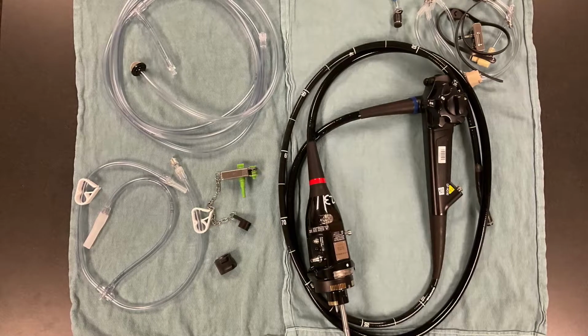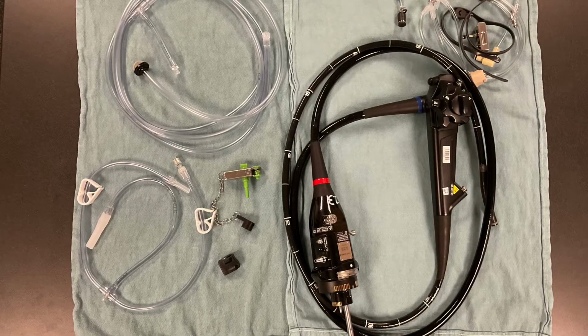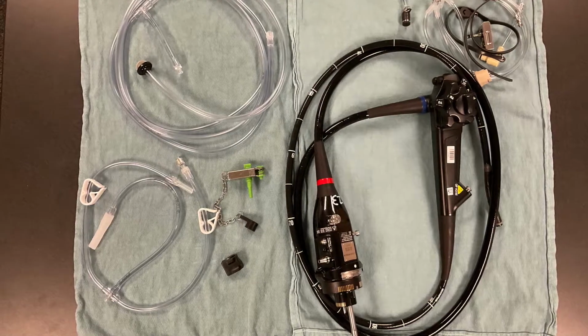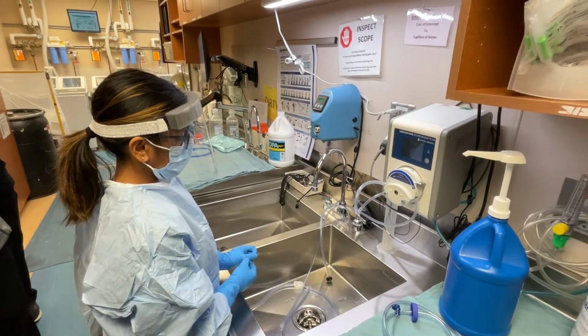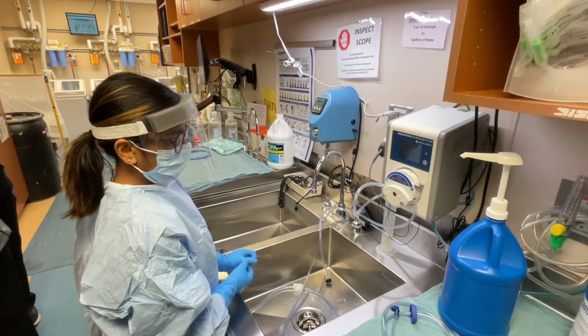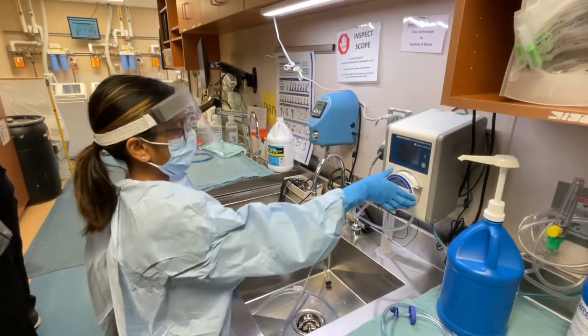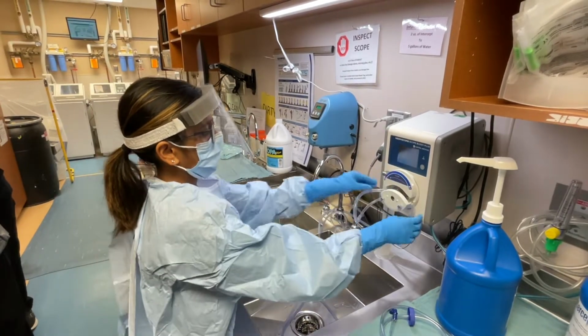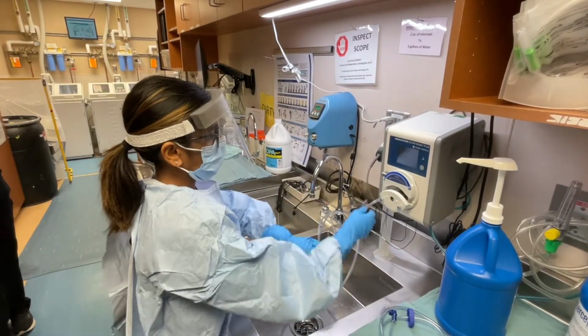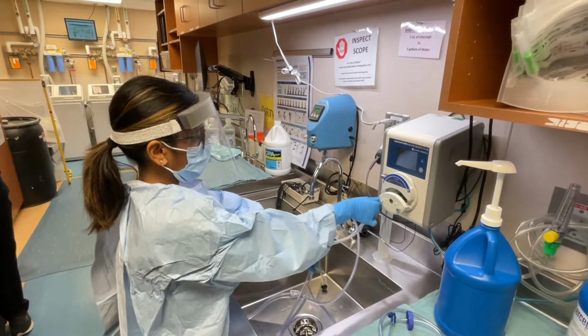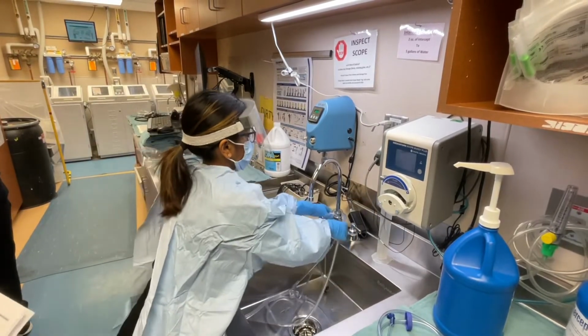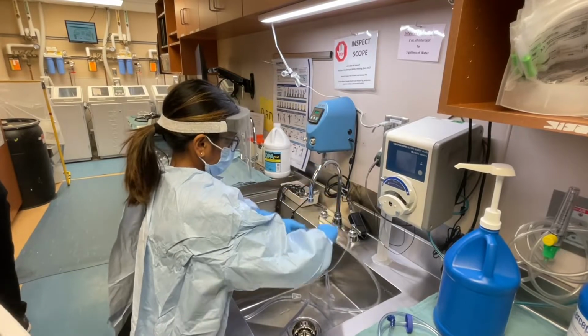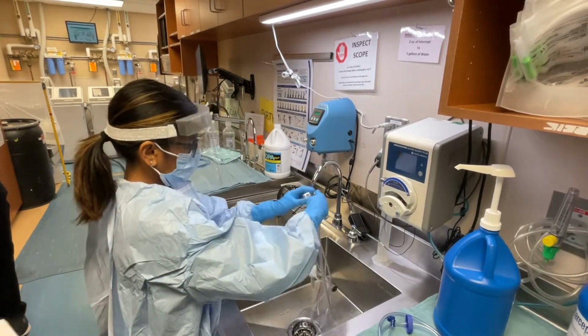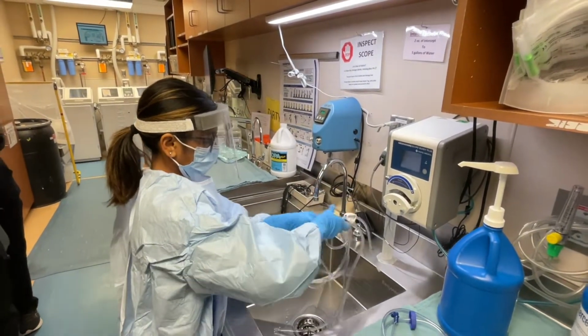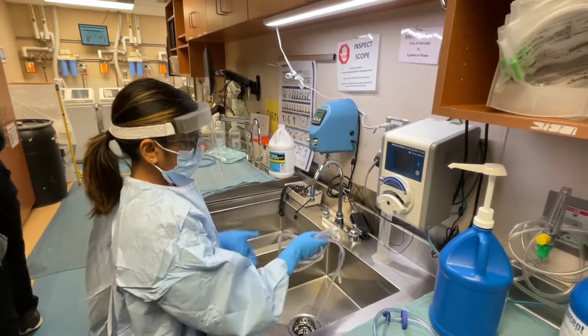This is the equipment you will need for a colon or EGD scope hookup for the Scope Buddy Plus. Today we are going to do the step-by-step guide for Scope Buddy Plus use. Remove old pump tubing, multi-use hookups, and the detergent out tubing. Discard this tubing into the regular waste bin. Tubing is good for 24 hours. When you come in during the overnight, the tubing that is there can be used. When you come in the morning, discard old tubing.